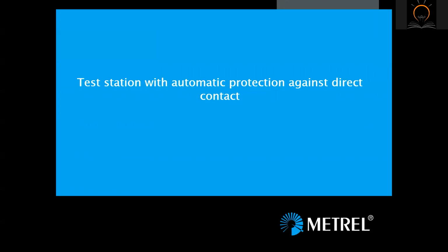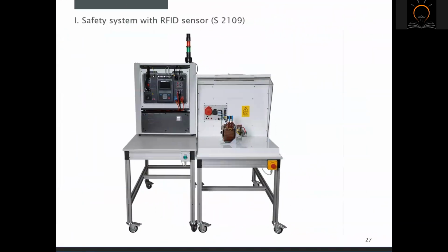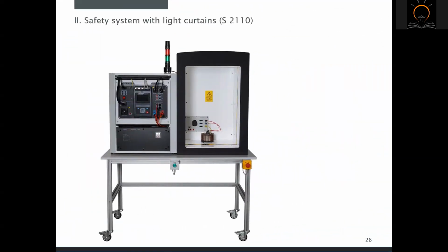against direct contact. Test stations built with enclosures such as test cages or hoods are the most commonly implemented option. This type of test station is typical in serial production lines, but is also preferred in workshops, repair and service shops. A test station with automatic protection against direct contact may be operated without the control and supervision of a skilled person. A test station using enclosures such as test cages without doors is the preferred solution for production with very high frequency of testing. The safety of such a system is assured with a light barrier sensor.